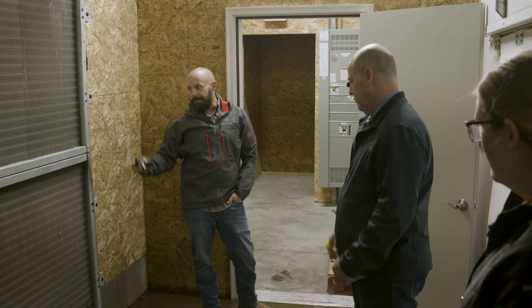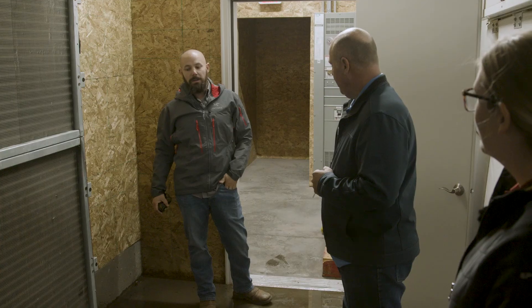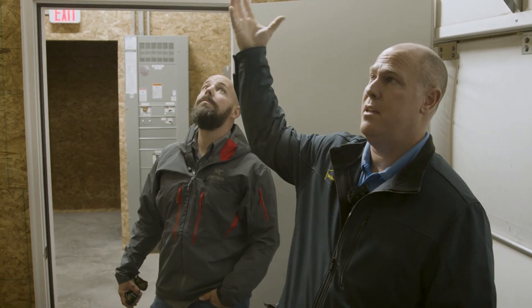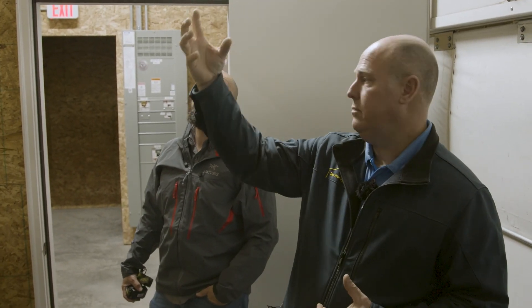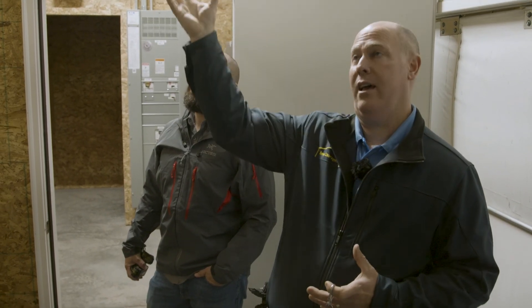So this moisture and the frost that's on the coils — that's what the bees are breathing, coming out of the hive. There's just a drain in the middle of the floor for all that water — a lot of bee breath. The air up above is the return air coming from the bees, and this is where we measure the CO2 level coming off the bees. It's using the bees as the heat source to mix with the cold, turning the refrigeration on and off to mix with the heat from the bees to get the right temperature.